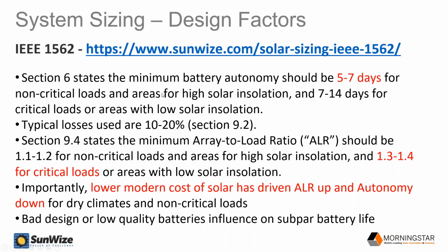All right, so as we talked about, I want to point people to IEEE 1562 if you're not aware of it. We have a tech note on this topic. It is the only published standard for off-grid system design that exists. If you reference this, you'll see that's where we're pulling this 5 to 7 days of battery backup. That's kind of the sweet spot for system design. And similarly for the ALR, this 1.3 to 1.4.